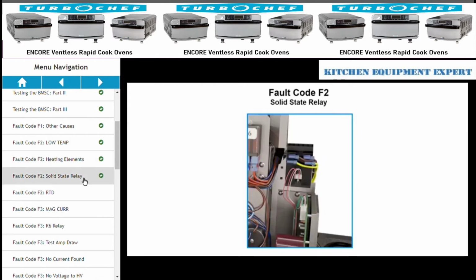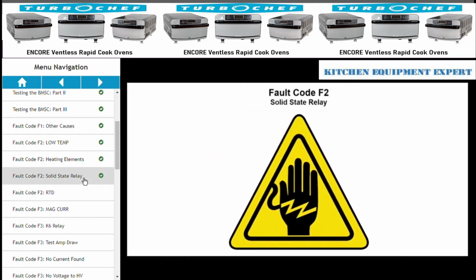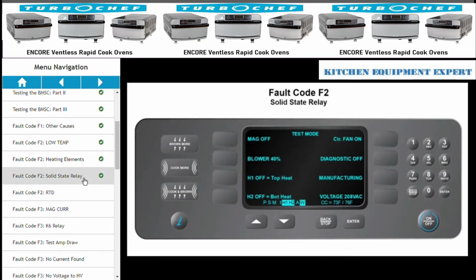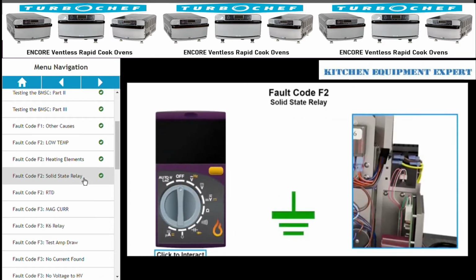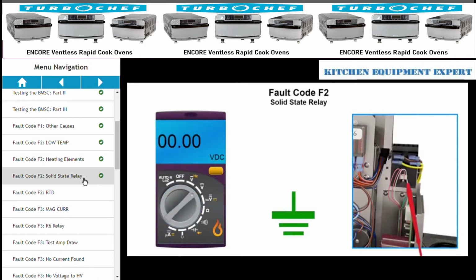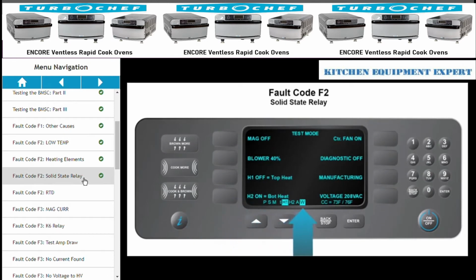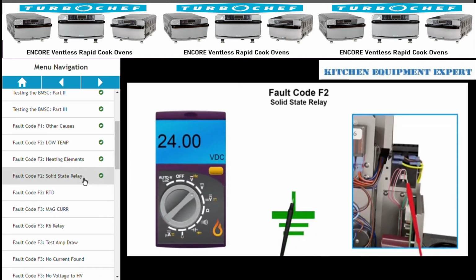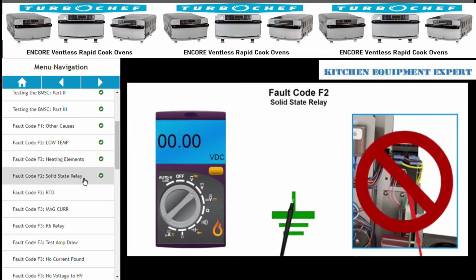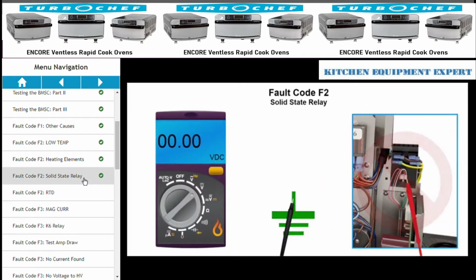The heating elements are controlled by a dual solid-state relay. This test must be done with the power on, so be careful. Put the oven into test mode. With your multimeter set to DC volts, and one probe on B-, and the other on a known ground, press the soft key to activate the elements. If you see the signal go from 24 to 0 volts DC, the signal is good, and the relay is defective. Repeat this with the bottom element circuit, using A-.